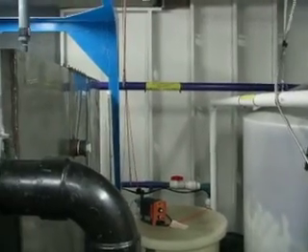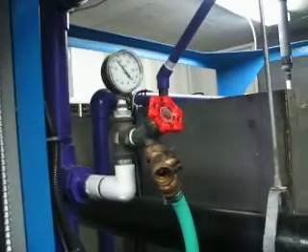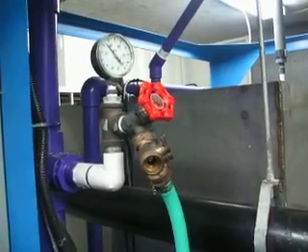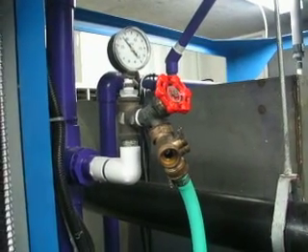And that's what these big barrels are — the cleaners? Yeah, exactly. These are all of the different stages of filtration. They're biological colonies of creatures that absorb food particles and different chemicals in the gray water and then clean it. We put it through a disinfection process. This is the first series of tanks, which are called Waterloo biofilters. And then in this stainless steel tank, it goes through a three-stage filtration — first through a coal medium, then through a sand, a slow sand filtration.